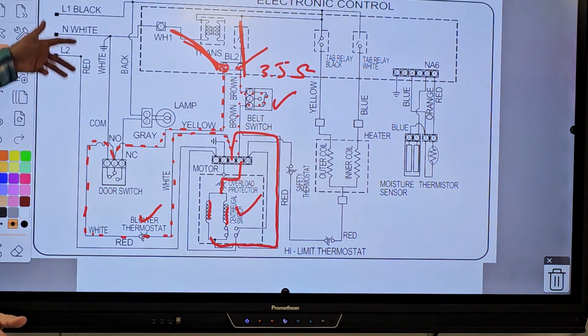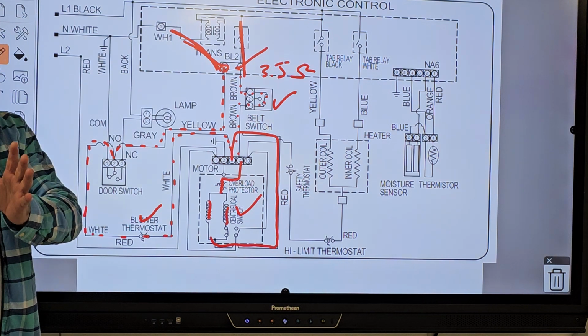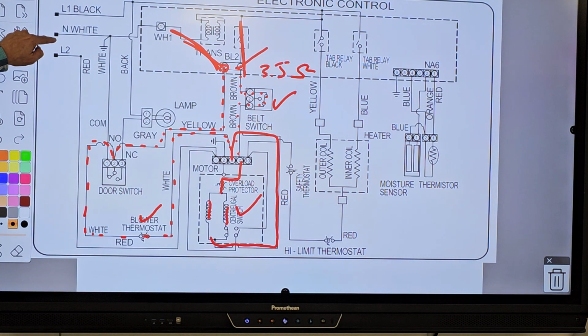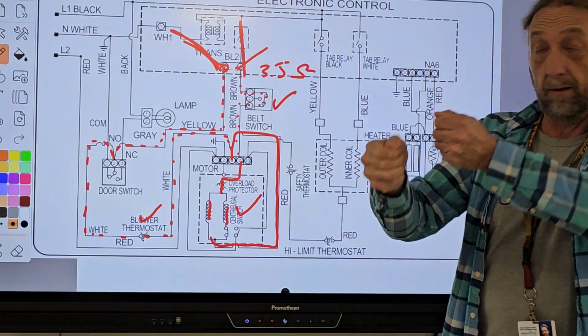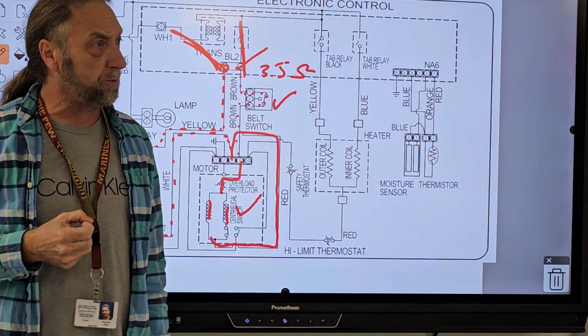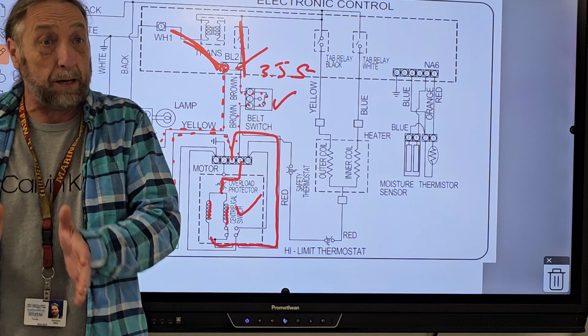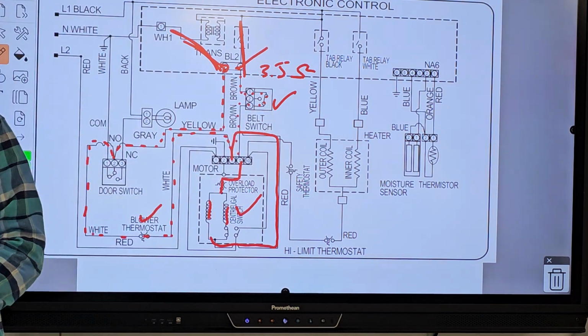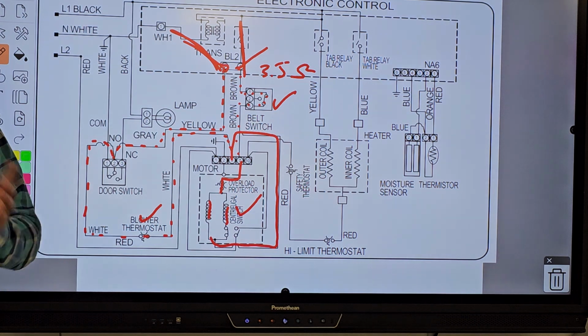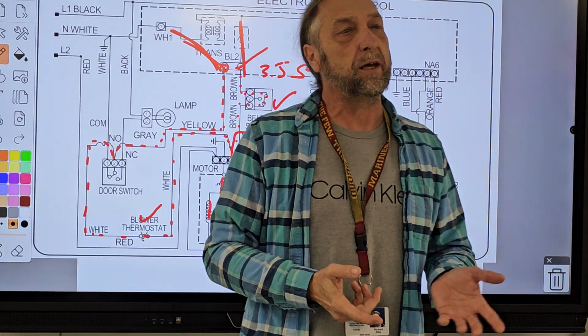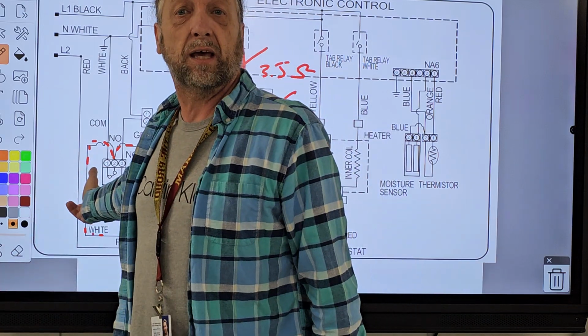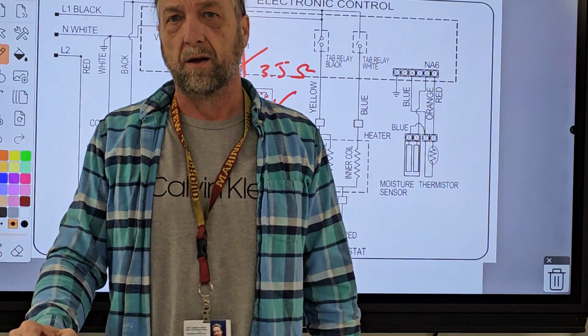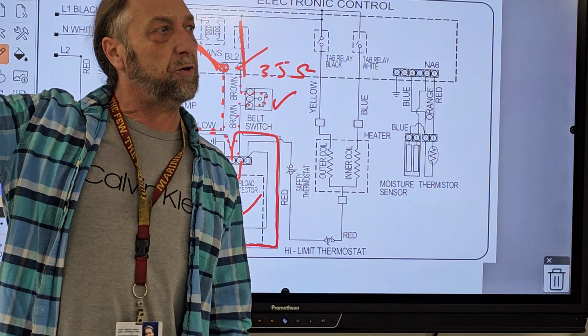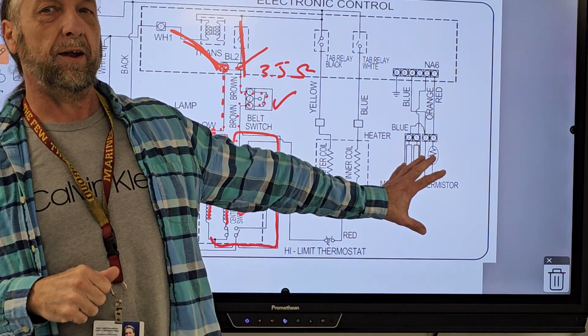Because even though this is a 240 volt outlet, what is this? Line 1 and neutral. In a 110 volt outlet, it's either line 1 and neutral or line 2 and neutral. So if I go to 2 or 3 different outlets and they're all giving me 120, but here I'm getting 107 volts, I know it's got to be 120. But I can go a step further, because telling the customer the voltage here is not the same, yeah, but the outlet's not the same. You know, customers come up with crazy answers. So, I checked the outlet in the wall, it's 120, but the dryer outlet's not 120.